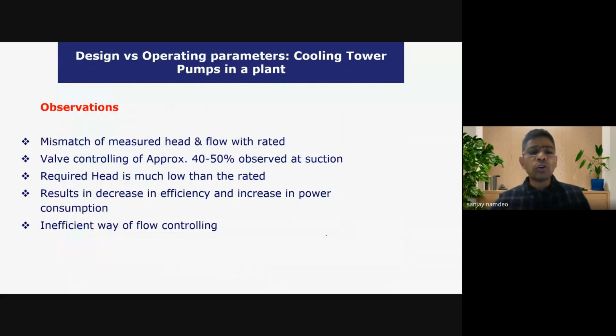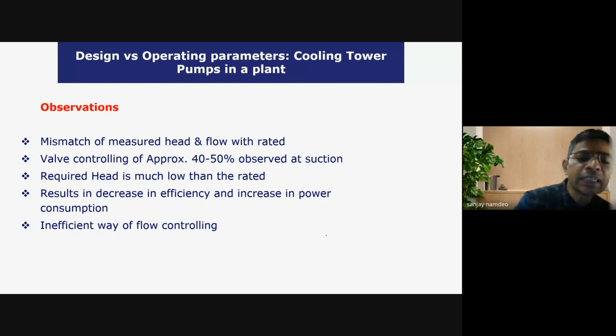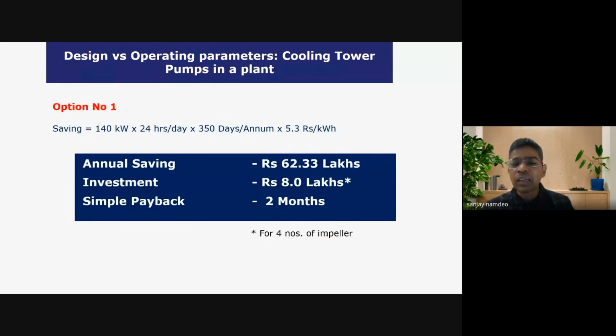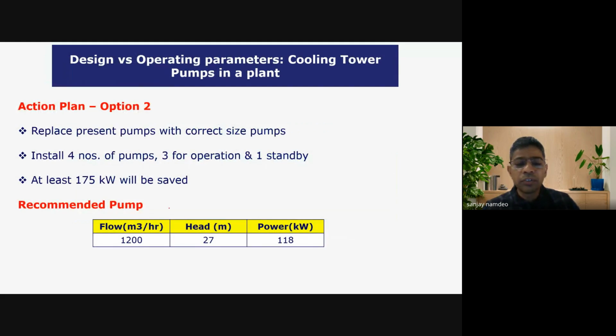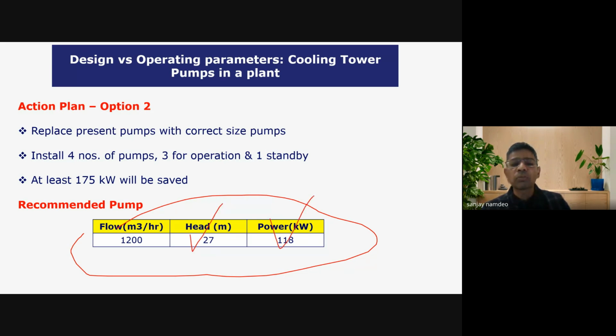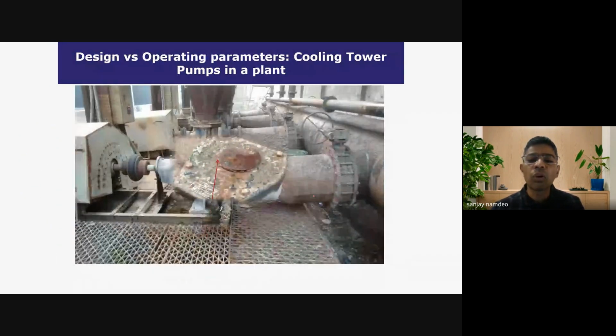So now the question is, what should have been the correct design of this pump? That we calculated. The correct design of this pump should be 1200 meter cube of flow, 27 meter of head, and only 120 kilowatt of motor capacity. So now you can well imagine the cost of a 1200 meter cube, 27 meter pump with only a 120 kilowatt motor, as compared to the present size. Present size is 1250 meter cube, 42 meter, and 200 kilowatt of motor. So if the company would have gone for the correct size of the pump, the investment would have been less as compared to the present investment for a 200 kilowatt pump, right?